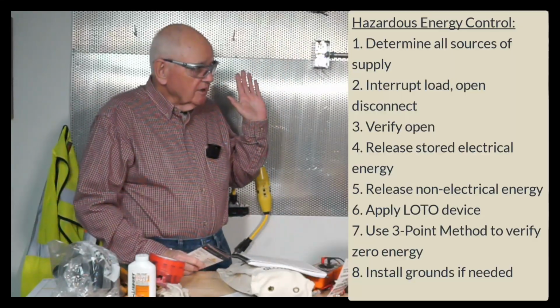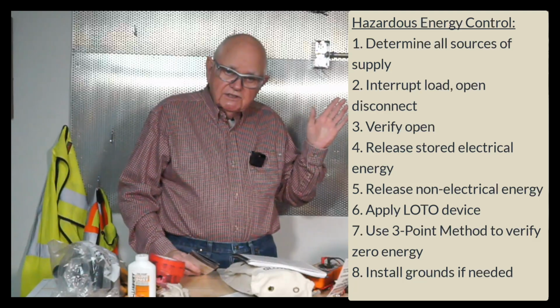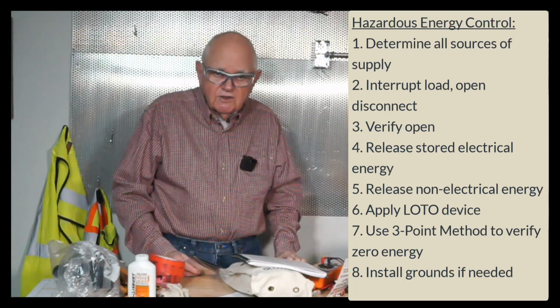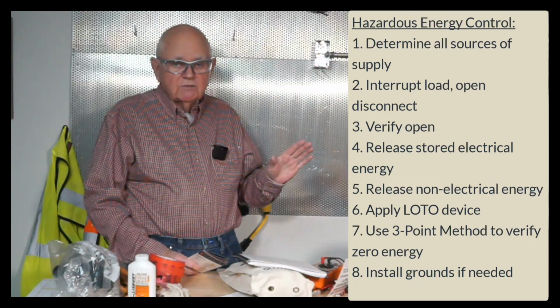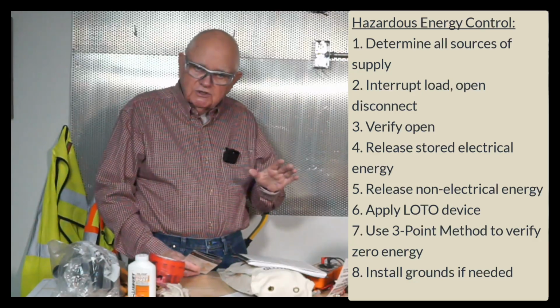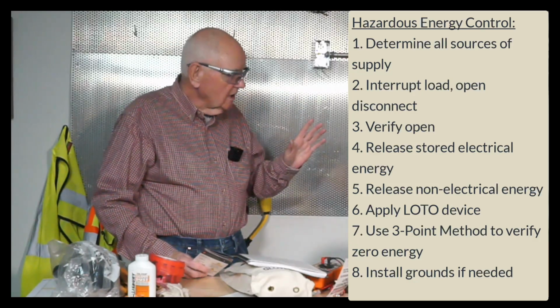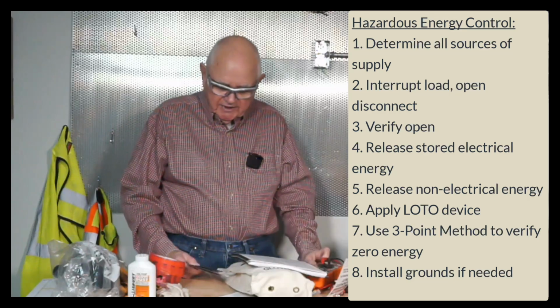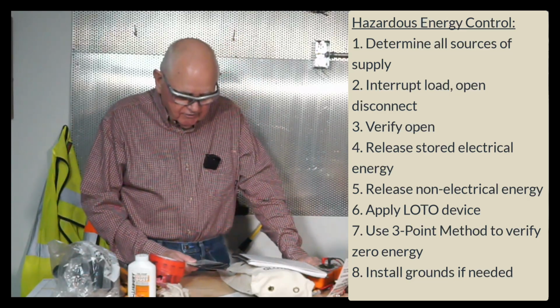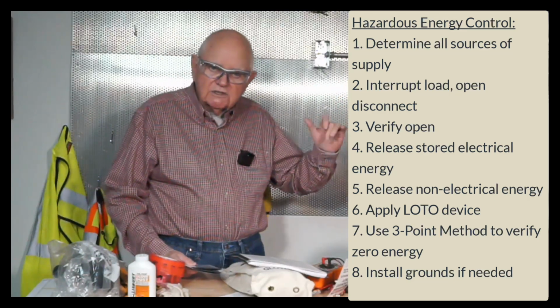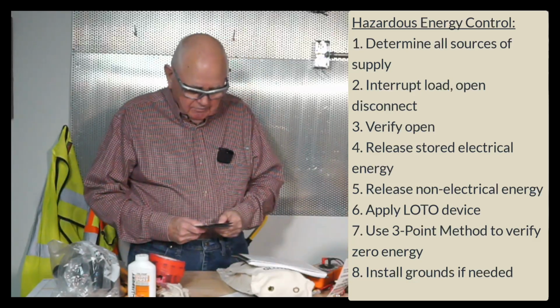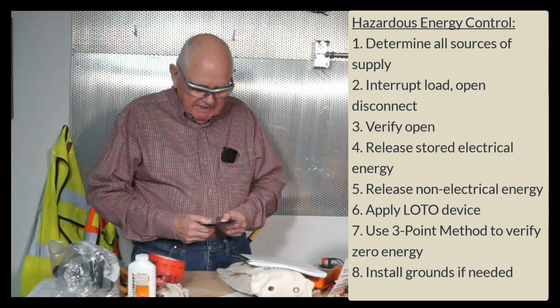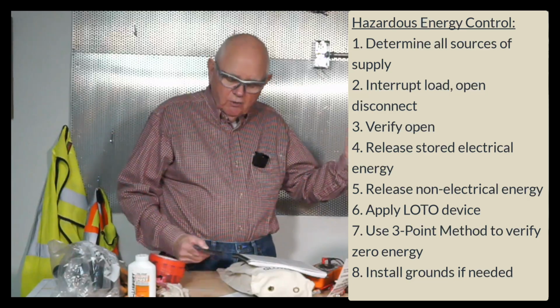And finally, the best thing you can do, of course, at any time is to establish an electrically safe work condition. So if I'm going to verify my equipment is in an electrically safe work condition, the first thing that I do is I determine all possible sources of supply. Walk down systems, of course, use your prints, up-to-date prints and so forth. Whatever it is you need to do, make sure you're not missing anything. Item number 2, after properly interrupting the load current, in other words, stopping the equipment, shutting the power off, open the disconnecting device for each source. I open the disconnecting device.